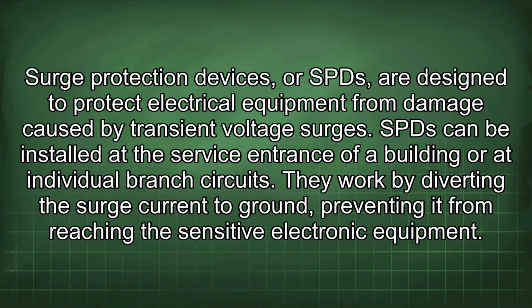Surge protection devices, or SPDs, are designed to protect electrical equipment from damage caused by transient voltage surges. SPDs can be installed at the service entrance of a building or at individual branch circuits. They work by diverting the surge current to ground, preventing it from reaching the sensitive electronic equipment.